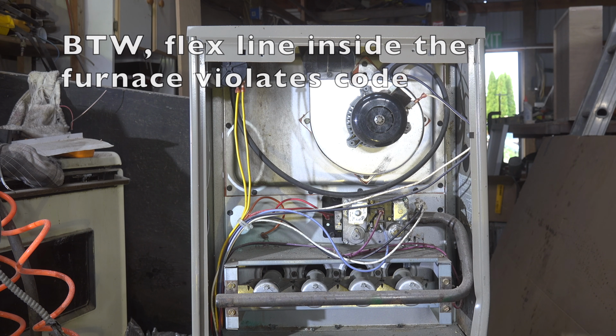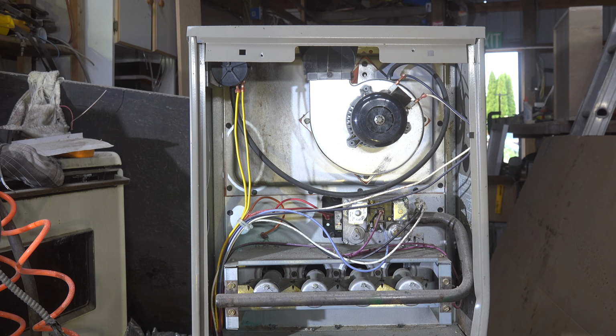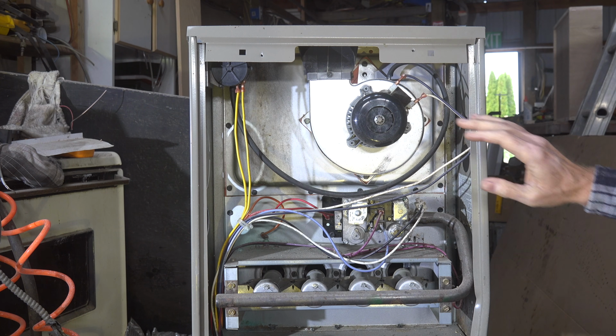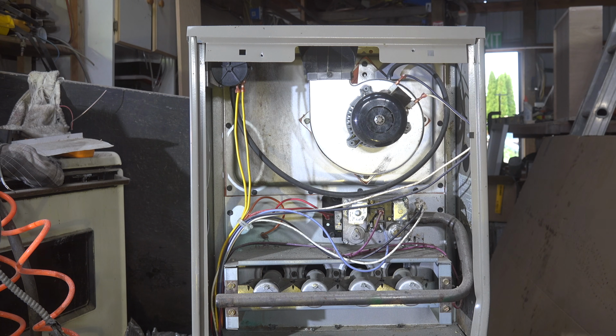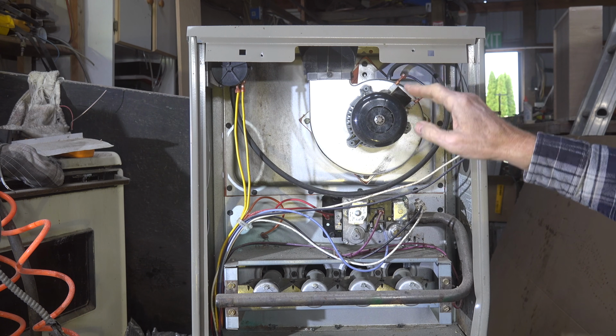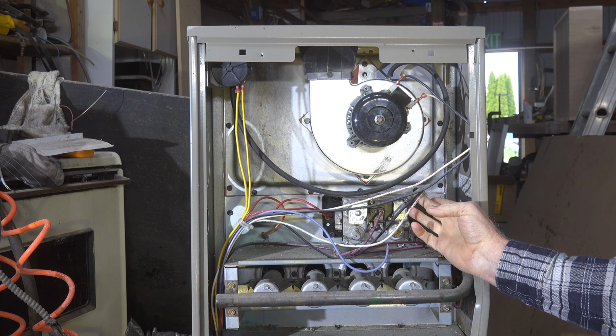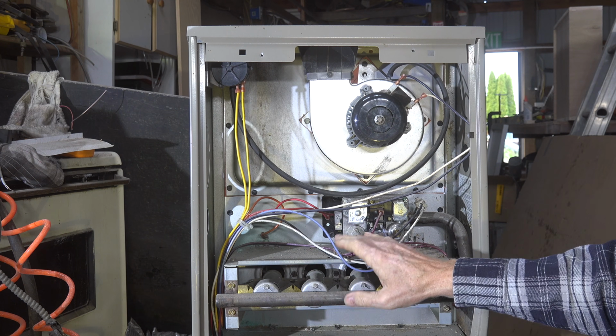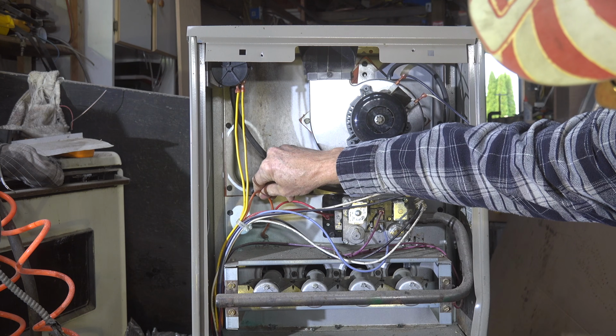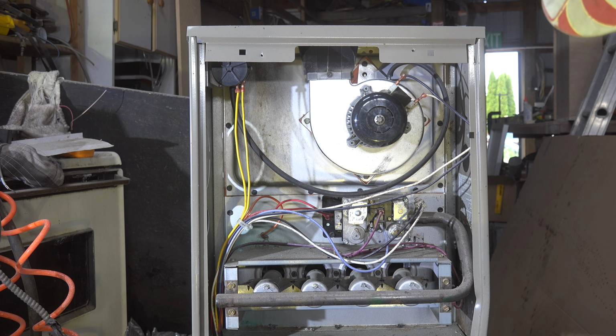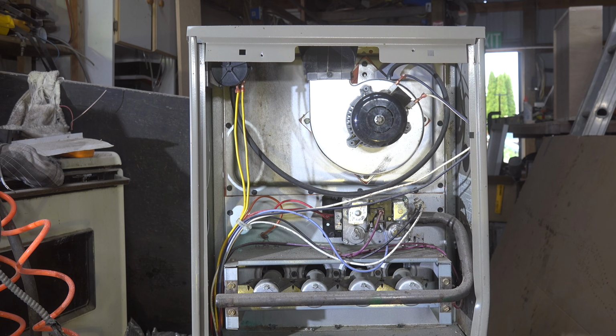The next thing I want you to do is take a picture of this with your phone, because these wires are going to have to be individually removed, and you want to be sure you put them back in the right spot. So take several pictures to be sure you've got all the angles. Here's the pressure switch, here's the inducer, here's the tubing going to the inducer, hot surface igniter wiring, and we have the limit switch wiring here and here. We have the flame sensor wiring there, and there's a limit switch right here that has to actually be removed. So I'd say go ahead and take a picture of this so you know how it goes back together when you put it back in.